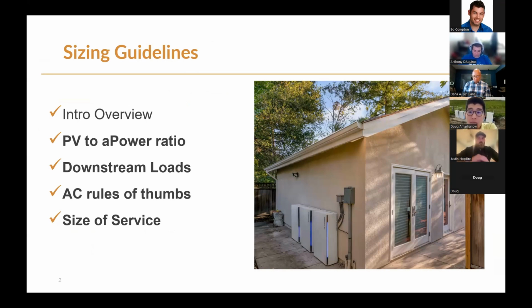The sizing of the system is very simple - it comes down to the factors on the screen right now: the PV to battery power ratio, meaning you can't connect a huge PV system to one battery; downstream loads, where you want to keep customers happy by giving them enough power; air conditioners, typically the largest load in the home, so you have to keep those in mind; and whether the home has 100 amp, 200 amp, or 400 amp service.